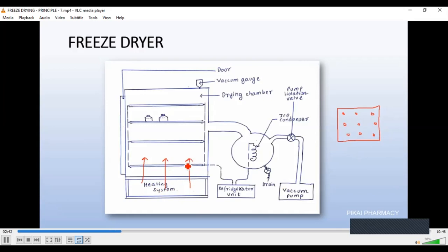It has to reach even the top plate very well. So we need this perforation so that the hot air can pass through these perforations and reach up to the top plate and dry the whole chamber in a uniform manner, so that the drying process becomes efficient.